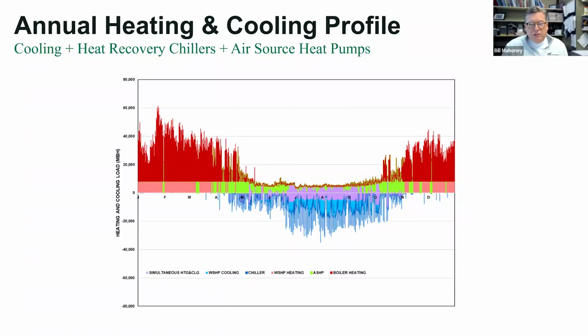So this was the profile of how we dispatch the equipment that we were recommending, which included mostly ground source heat exchangers, but we also had backup because they couldn't do the whole load. We had backup from potentially using some of the steam in a heat exchanger that's available from the cogen plant. We also looked at condensing gas boilers, and we looked at air source heat pumps.